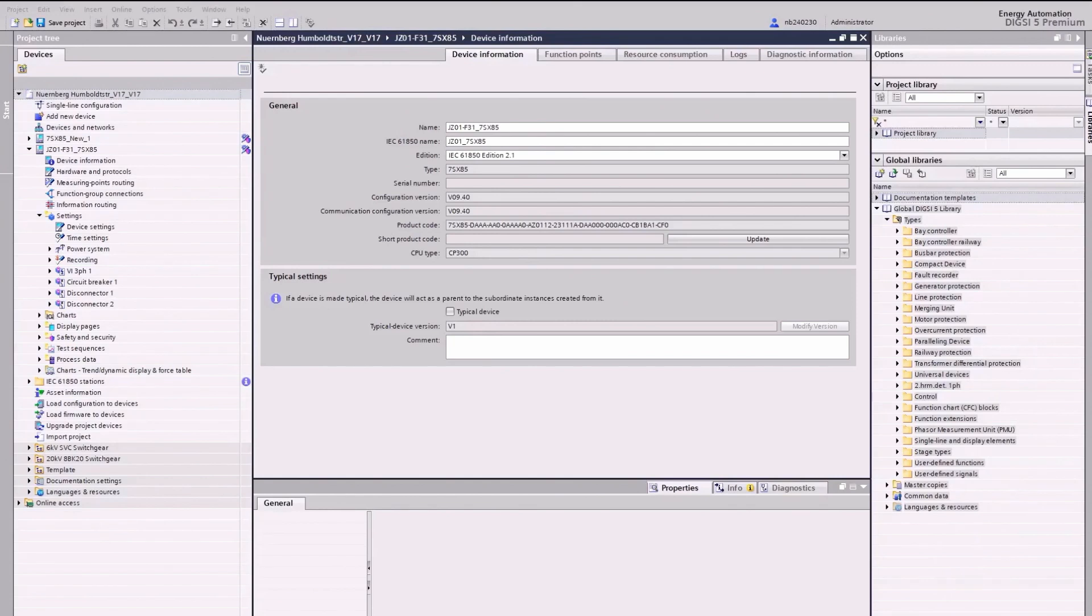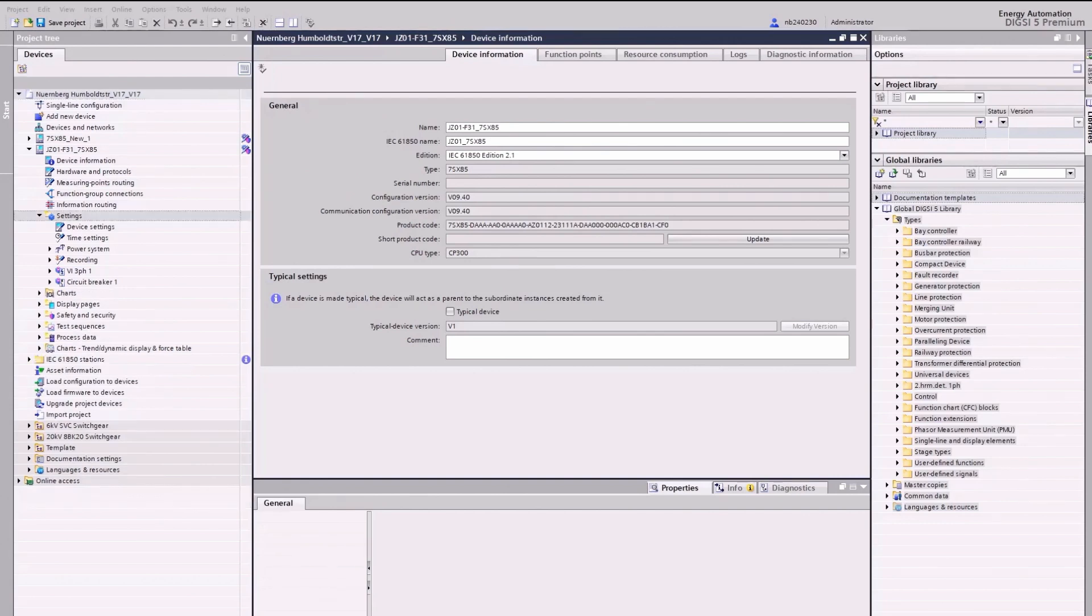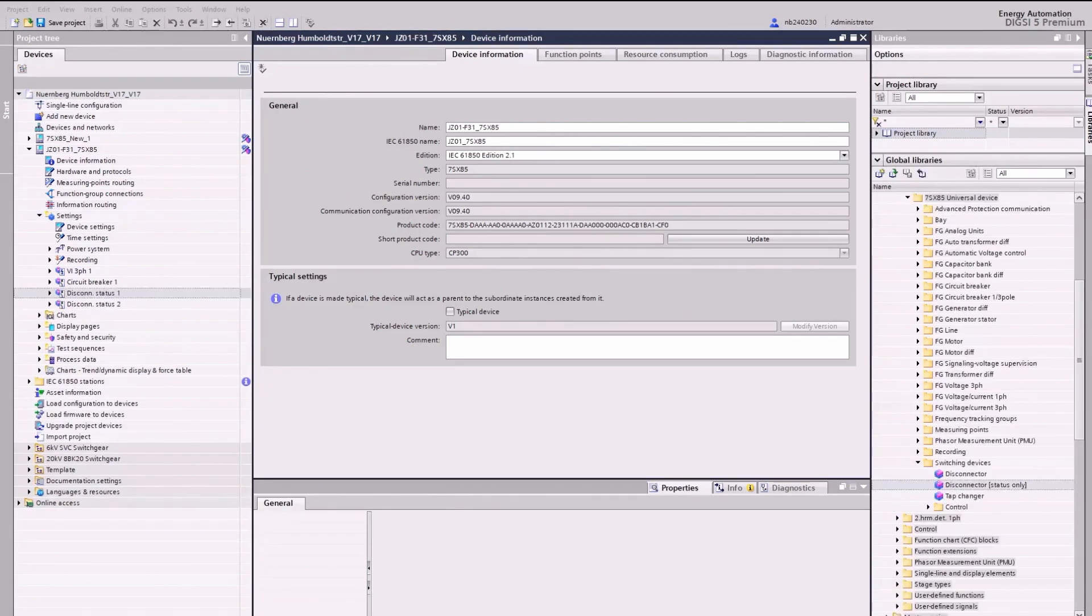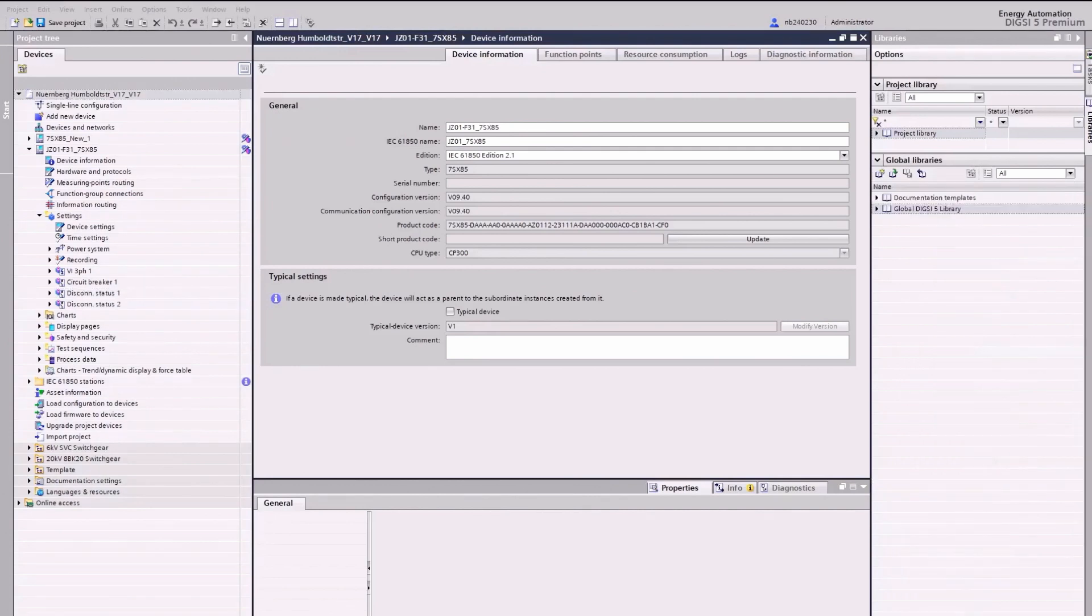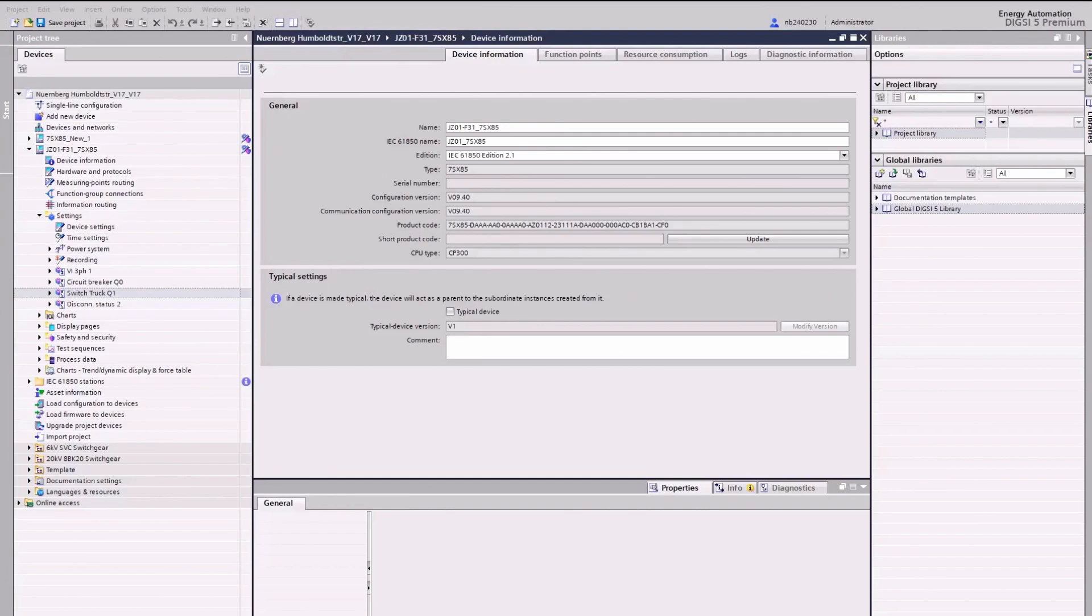The pre-configured disconnector 1 and 2 are controllable ones. In our case, we need only the status information. Therefore, we exchange it with the switching device's disconnector status only. For a better understanding, we rename the name of the circuit breaker and switching devices. Circuit breaker 1 in circuit breaker Q0, disconnector status 1 in switch truck Q1, and disconnector status 2 in earthing switch Q8.